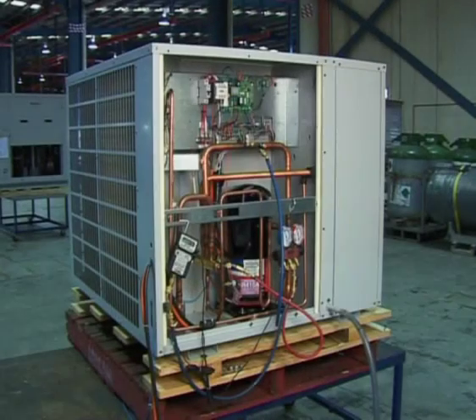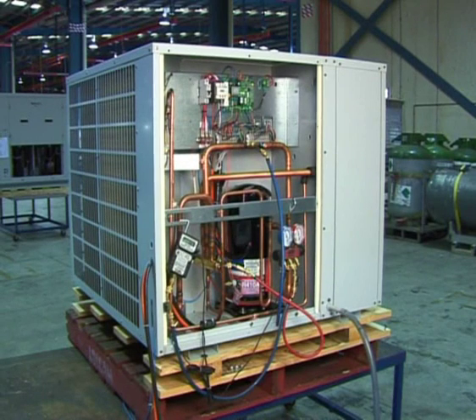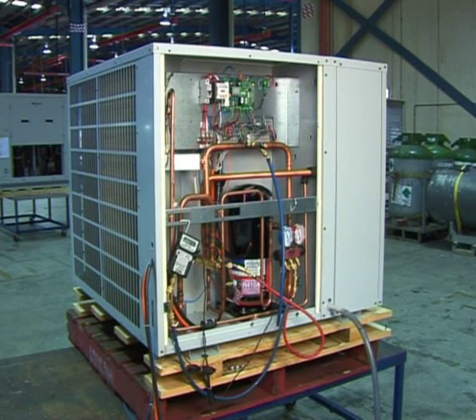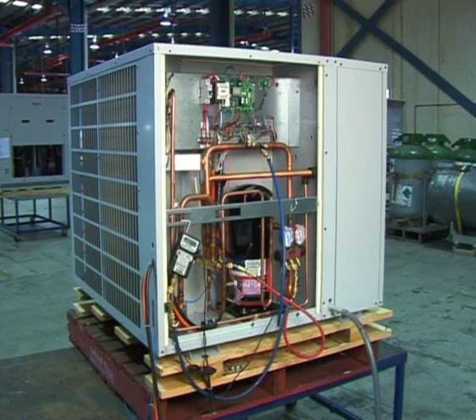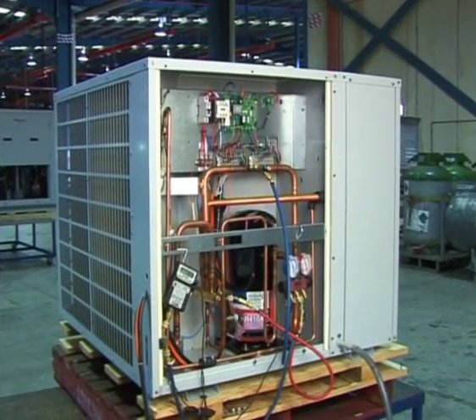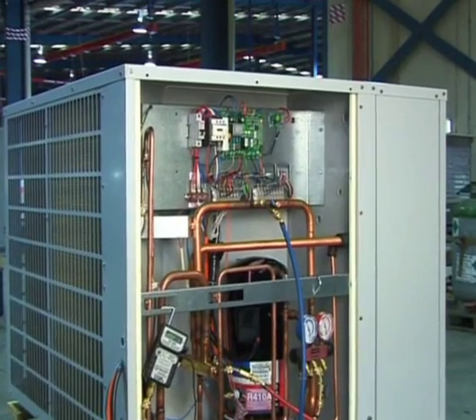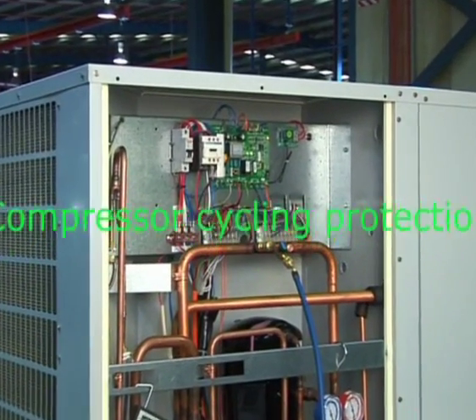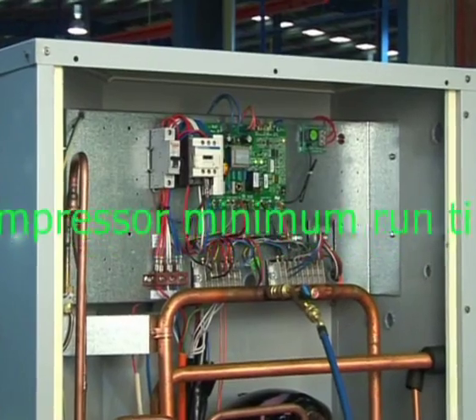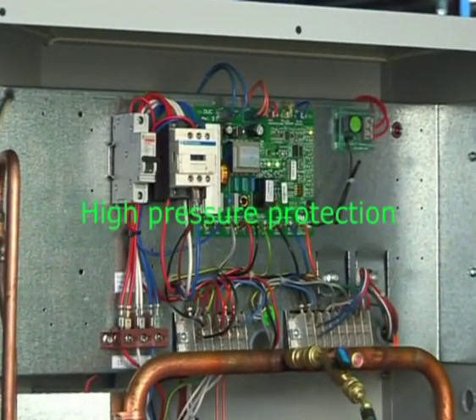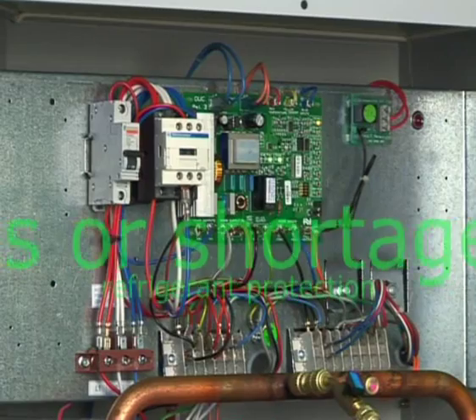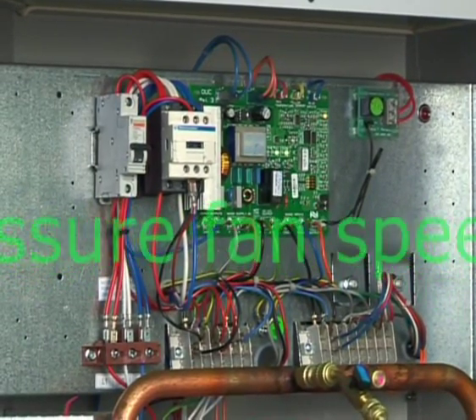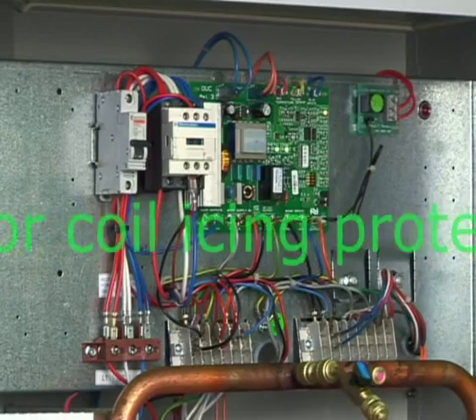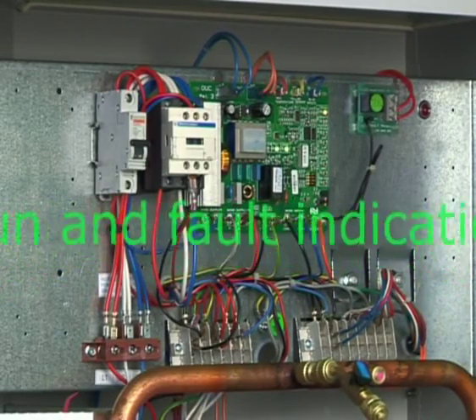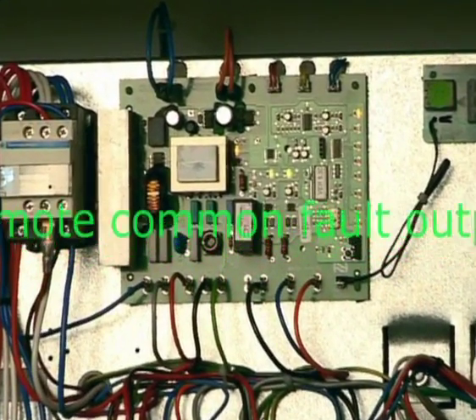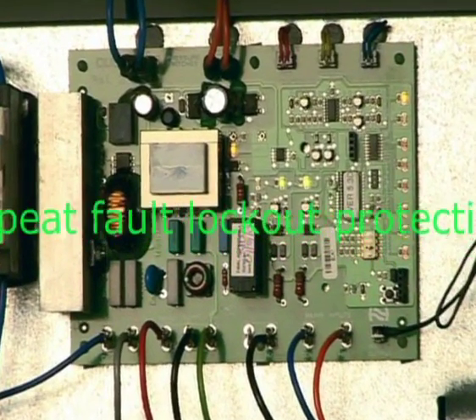The Temperzone Outdoor Unit Controller, or OUC as it is commonly known, is a pre-programmed electronic controller of the outdoor unit's refrigeration system, complete with system protection features. The features that the OUC encompasses are compressor cycling protection, compressor minimum runtime, high pressure protection, low pressure protection, loss or shortage of refrigerant protection, head pressure fan speed control, indoor coil icing protection, run and fault LED indication, remote common fault output, and repeat fault lockout protection.